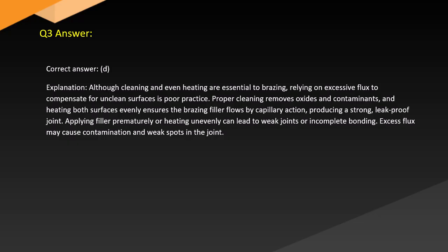Although cleaning and even heating are essential to brazing, relying on excessive flux to compensate for unclean surfaces is poor practice. Proper cleaning removes oxides and contaminants, and heating both surfaces evenly ensures the brazing filler flows by capillary action, producing a strong, leak-proof joint. Applying filler prematurely or heating unevenly can lead to weak joints or incomplete bonding. Excess flux may cause contamination and weak spots in the joint.